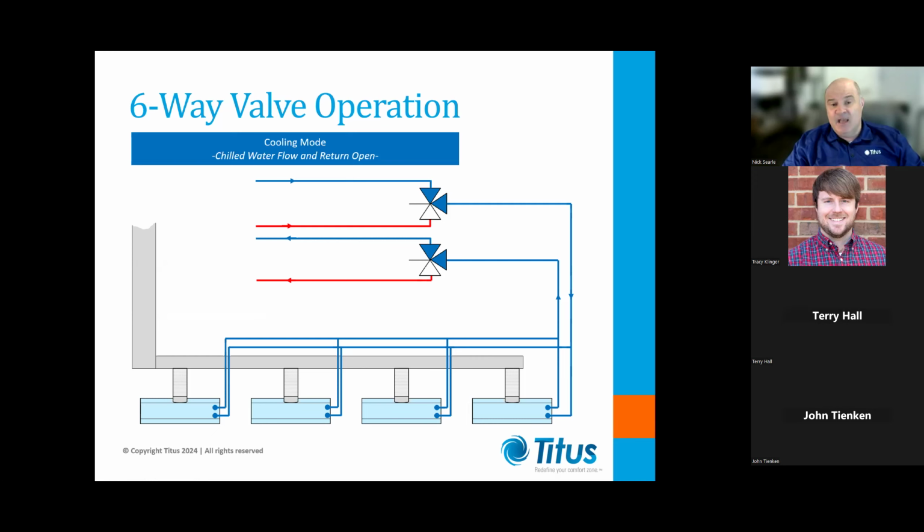So what will happen is a single actuator that's controlling the 6-way valve, so it's controlling both heating and cooling water, will rotate through to its halfway position, its deadband position. So all 6 valves are now closed. So no water at all is running through the chill beams.